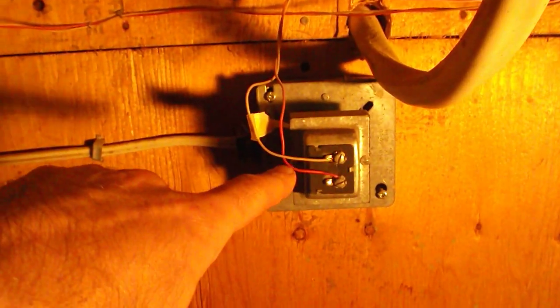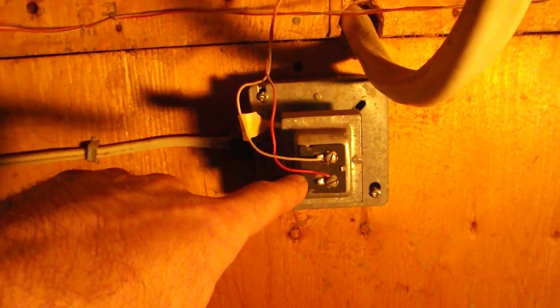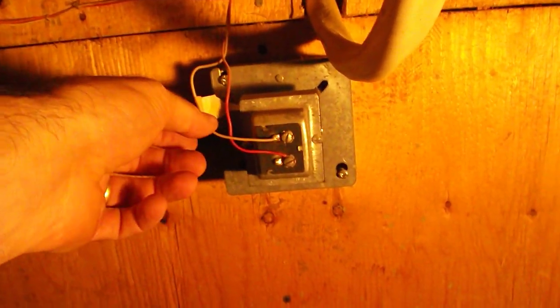I think this is a 24 or 28 volt AC transformer, and while we're here looking at it, the original problem was found today with a broken wire right here. It's kind of fragile in this location, vulnerable, and something bumped it and broke it off.